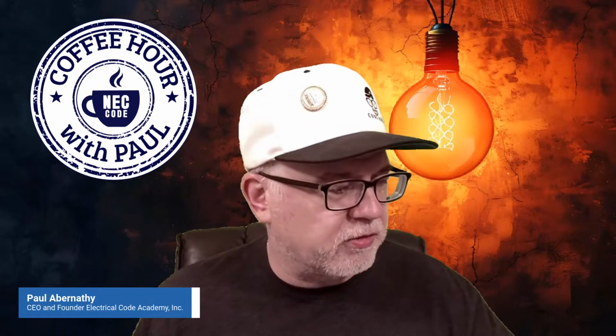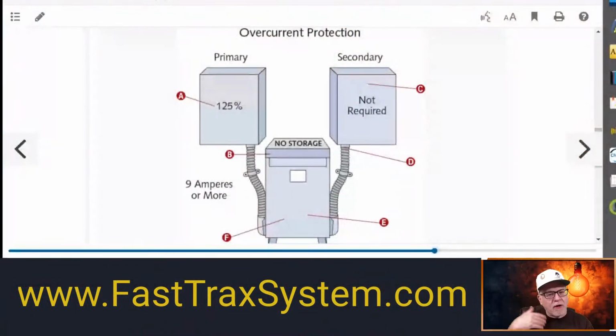So let's get back to this lesson really quick. Okay, let's look at this one. These are based on our figures, based on what we discussed. This would be this transformer. If we were doing this one and happened to apply this rule where we have primary only protection and no secondary protection, then what we want to do is the primary protection up to 125%. So let's say this was a 90.21 amp transformer. That would be the amps on the primary side. We already did that math. If you're coming in late, we did 75,000 divided by 831.36, because 831.36 is where you take the 480 times the square root of 3. That's how we get it. In the real world, if you just want to drop it to 831, you're going to be fine. It's going to get you close enough.